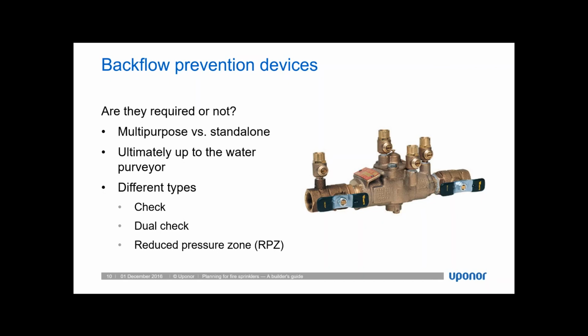It is very important, though, to try to talk to that water purveyor. If they're requiring a backflow preventer, you should ask the question, would this be required if this was not supplying a sprinkler system? If the answer is no, then you move into, well, is this a standalone or multi-purpose? Because if it's a multi-purpose sprinkler system, every component is rated for potable water and is completely lead-free. And if installed correctly, there should be no stagnant water in your multi-purpose sprinkler system. Therefore, a backflow prevention device should not be required.